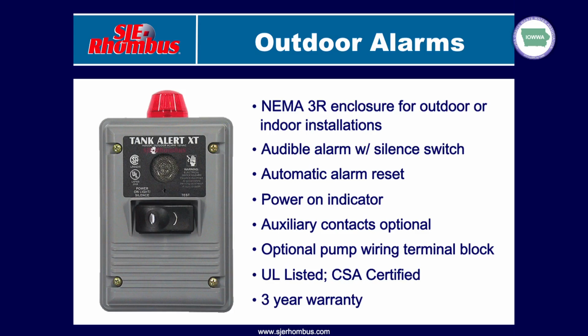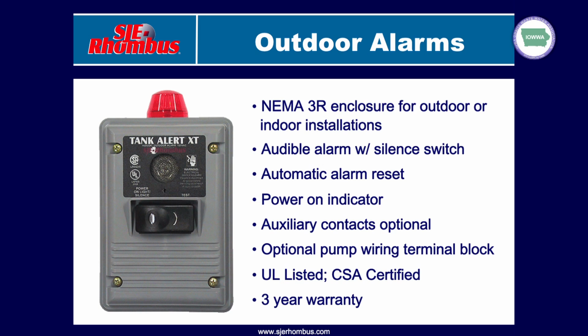Here's an example of one of our outdoor alarms. With an outdoor alarm, you're going to be looking for a NEMA 3 or greater rating on the enclosure. That basically says that it's intended for outdoor installations. Blowing precipitation is not going to negatively affect it. It's also intended for installations where you may get temperature extremes. And again, we're just going to pop through some of these. A lot of the same features that we look for in an indoor alarm, we'd also attribute to an outdoor alarm as well.